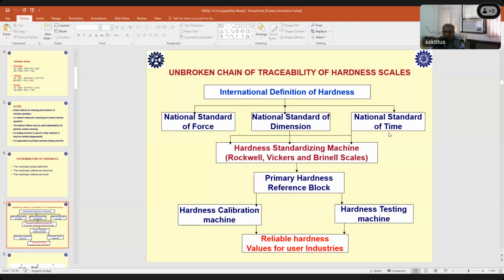Again, we are applying the force for a particular time. So you have to make sure whatever the time, whether it is 4 seconds, sometimes 10 to 15 seconds, all these should be independently traceable to the national standard. These three factors are involved in hardness measurement; though it's an empirical number and not a unit, these components are all defined units. So these play a role, and all three components should be independently traceable to the national standard. Then with these parameters, we achieve the hardness standardizing machine in Rockwell, Vickers, Brinell. Once you achieve all these independently and establish a machine, that machine we can call a primary hardness standard. Once the primary hardness standard is established, with the force, dimensional component and time independently traceable to the national standard, we can call it a primary hardness machine.